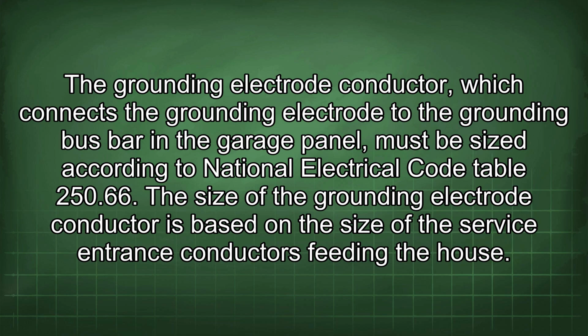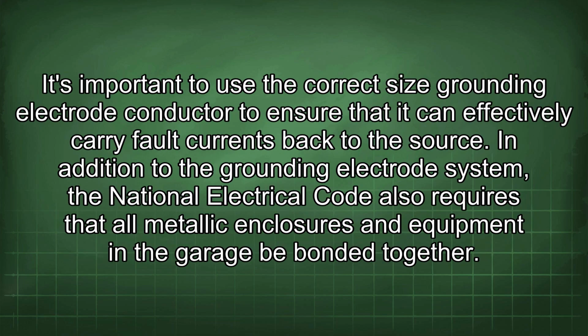The grounding electrode conductor, which connects the grounding electrode to the grounding bus bar in the garage panel, must be sized according to National Electrical Code Table 250.66. The size of the grounding electrode conductor is based on the size of the service entrance conductors feeding the house.